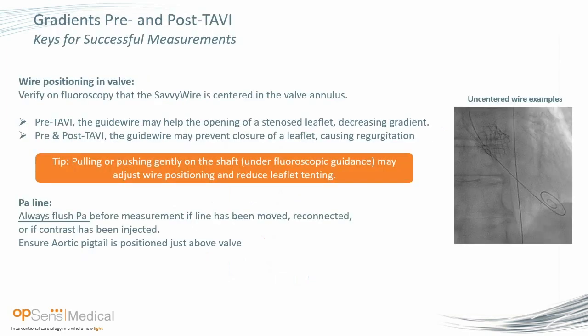So it's important that the wire positioning in the valve is done in a fastidious manner for a number of reasons. One, obviously, to safely deliver the valve. That's just the standard application across all TAVR delivery wires. But importantly, you want to make sure that the wire is not pinning open, causing aortic regurgitation, but also that that sensor is located in an appropriate place. And you want the wire to be in a stable position so you're not causing too much ectopy and affecting the different transduced gradients. You want to make sure that you flush the line like you would with any line.